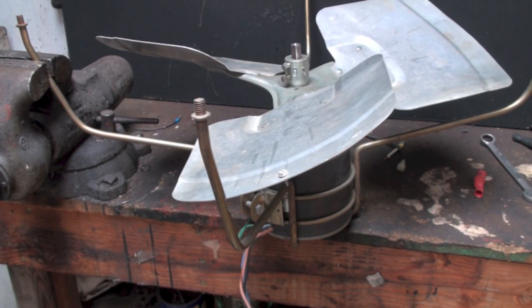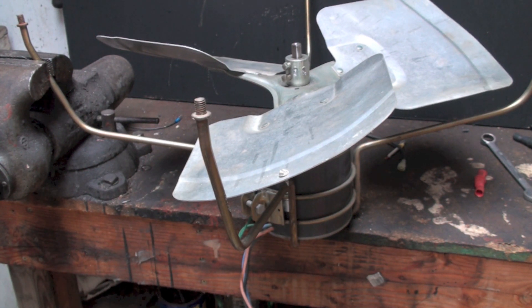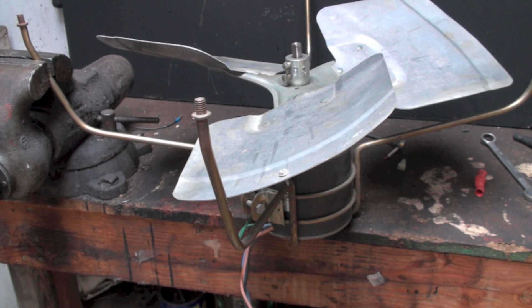Okay, I've come out on a job, let's say the fan's out of balance. I may have replaced the motor, I may not have, depending on what's going on. But let's say the fan blade isn't readily available. Now normally, I don't use general replacement fan blades, because it's too hard to figure the pitch, and there's assorted hubs and the like to use with them. They're a pain in the tail end.